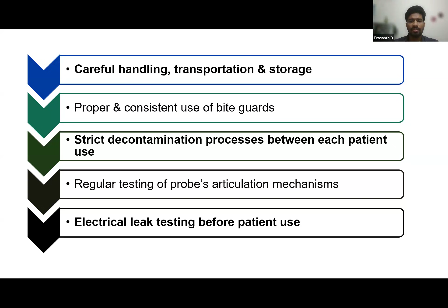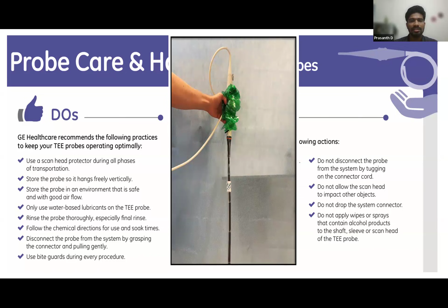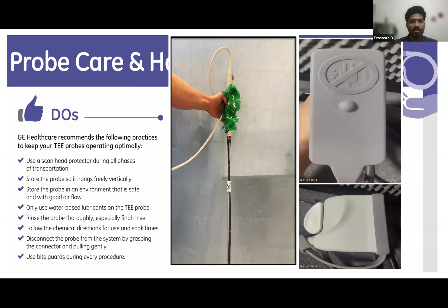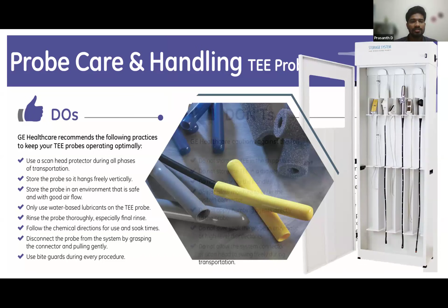So these are the do's and don'ts of the TEE probe. Always use a scan head protector during all phases of transportation. Like here they are covering the control housing with a plastic sheet, and the connector end should be closed properly whenever not in use, and store the probe so that it hangs freely. The silicone cover should be put on the tip, and it should hang freely and vertically, stored in an environment with good airflow, and always use only water-based lubricants.